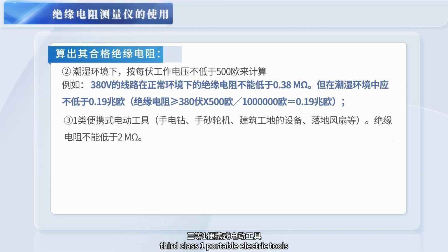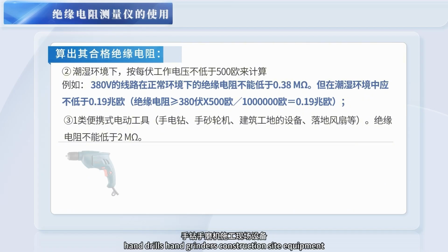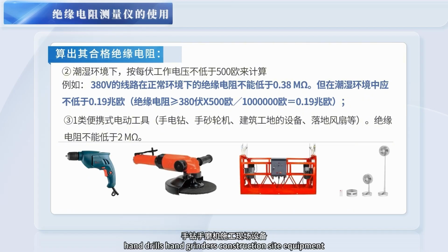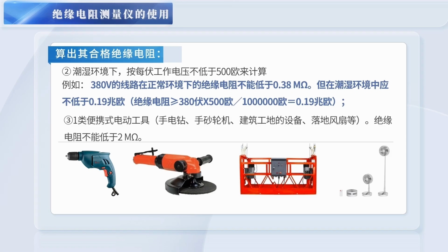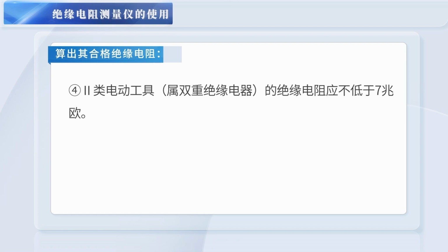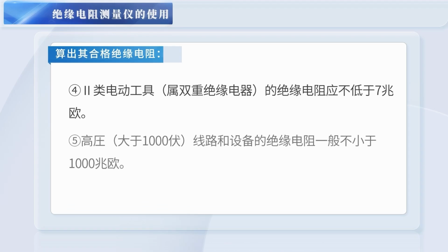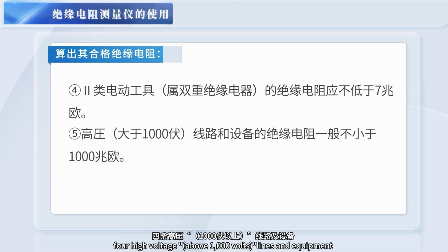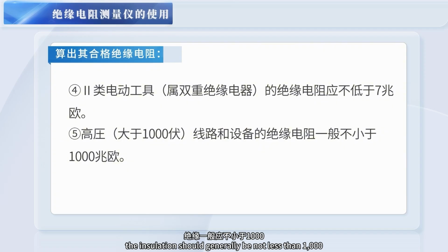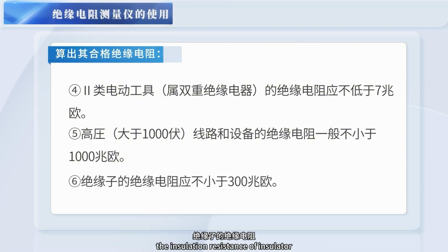Third, class 1 portable electric tools, such as hand drills, hand grinders, construction site equipment, and floor fans: the insulation resistance should not be less than 2 megohms. Fourth, class 2 power tools, which are double insulated: the insulation resistance should not be less than 7 megohms. Fifth, for lines and equipment above 1000 volts, the insulation should generally be not less than 1000 megohms. Sixth, the insulation resistance of an insulator should be not less than 300 megohms.